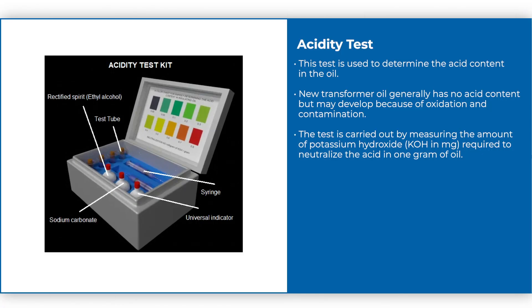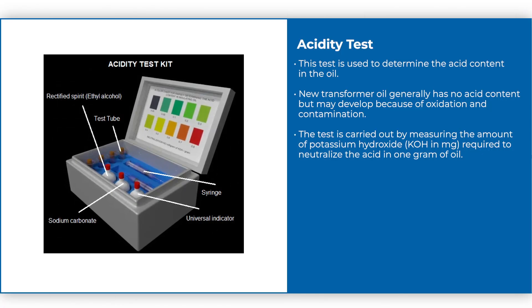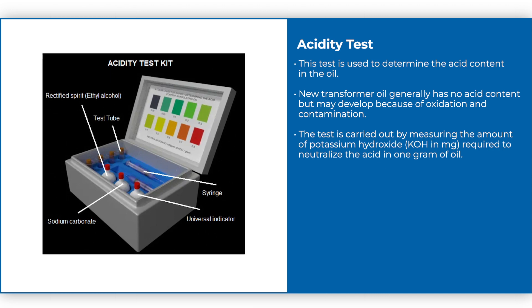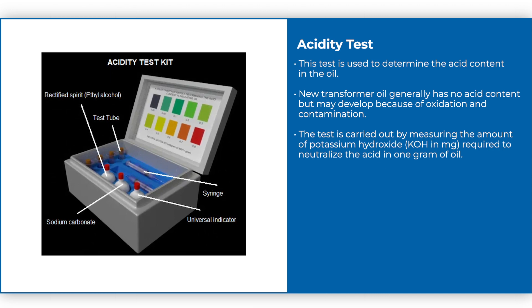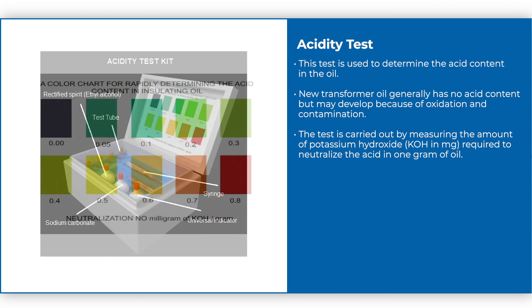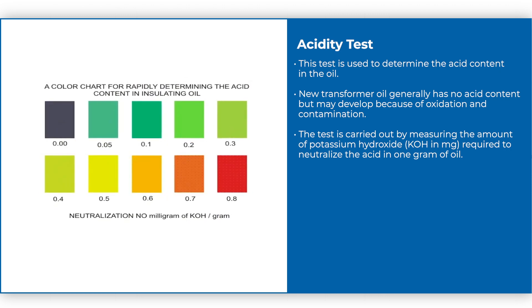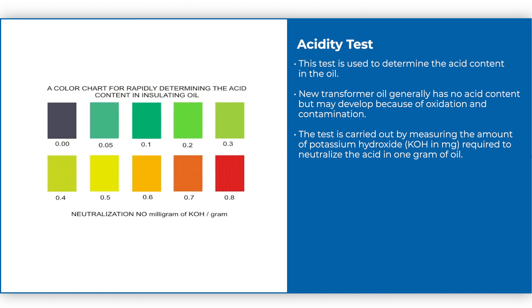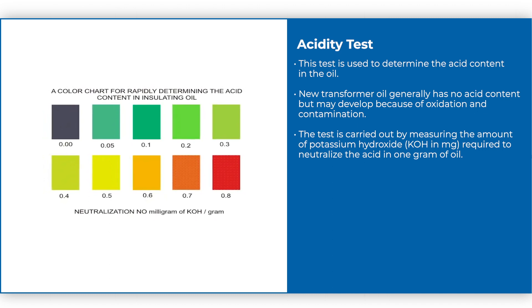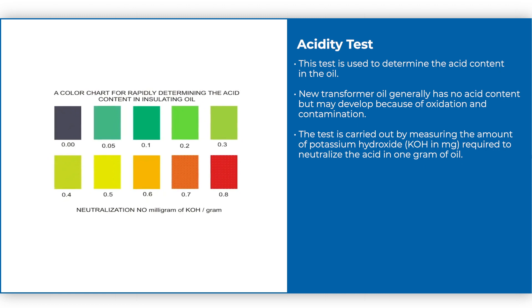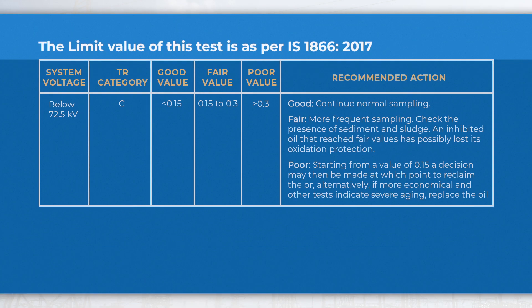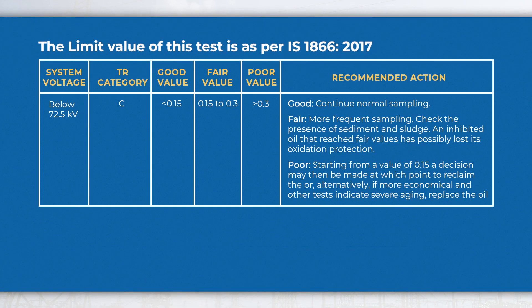Acidity test: This test is used to determine the acid content in the oil. New transformer oil generally has no acid content but may develop acidity because of oxidation and contamination. The test is carried out by measuring the amount of potassium hydroxide (KOH) in mg required to neutralize the acid in 1 gram of oil. The limit value of this test is as per IS 1866:2017, given in the table.